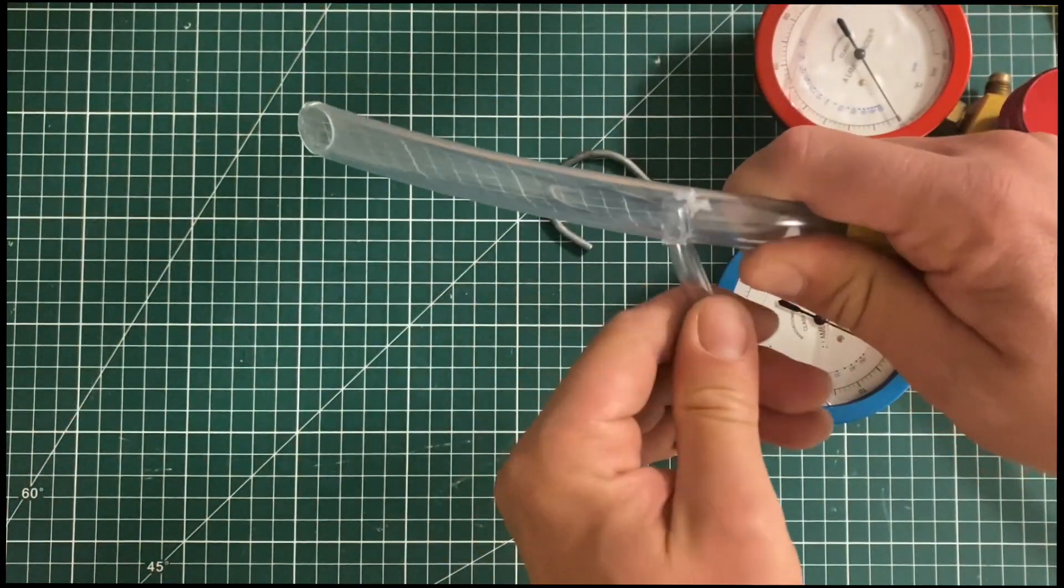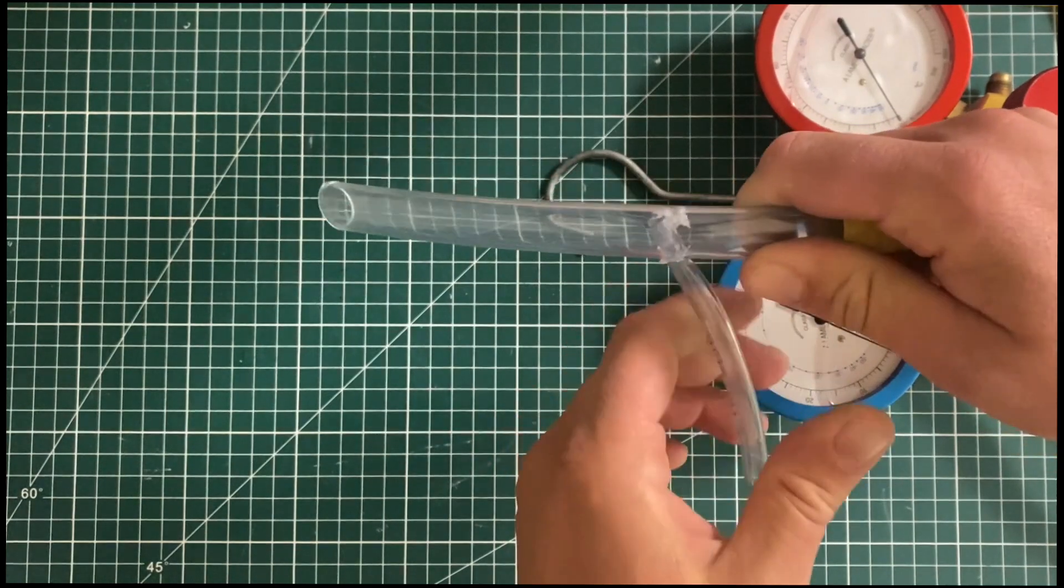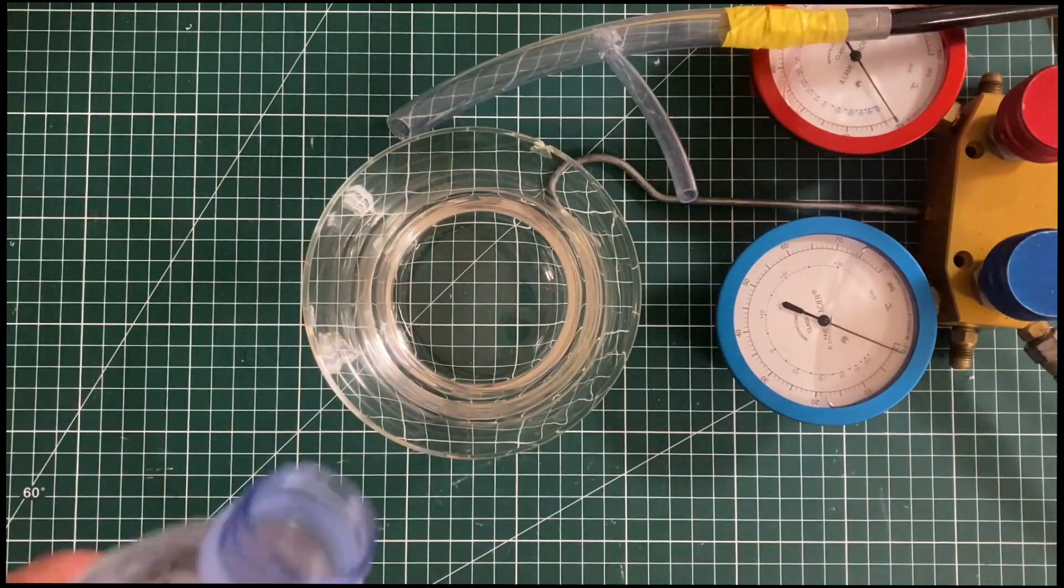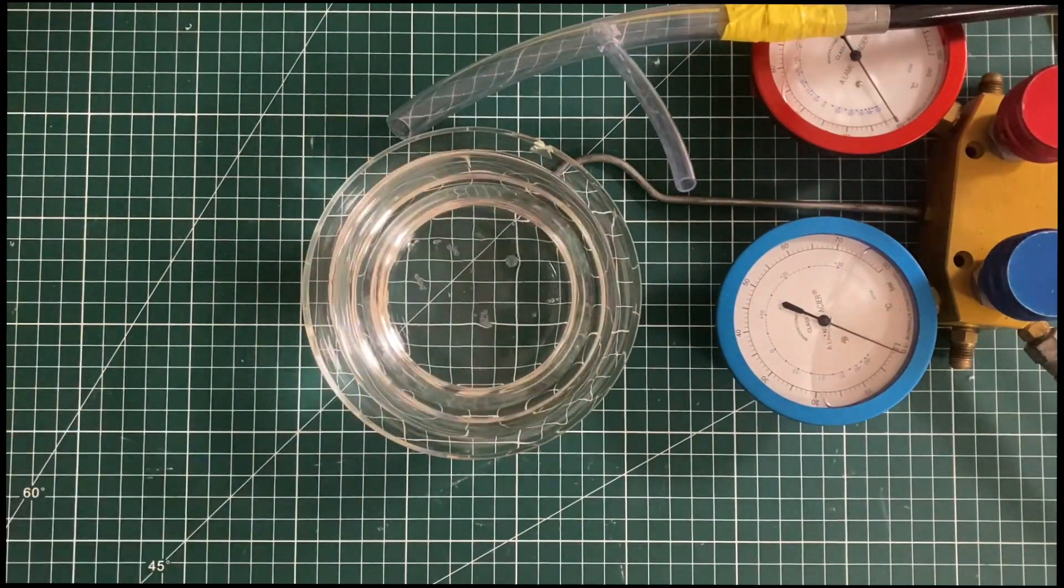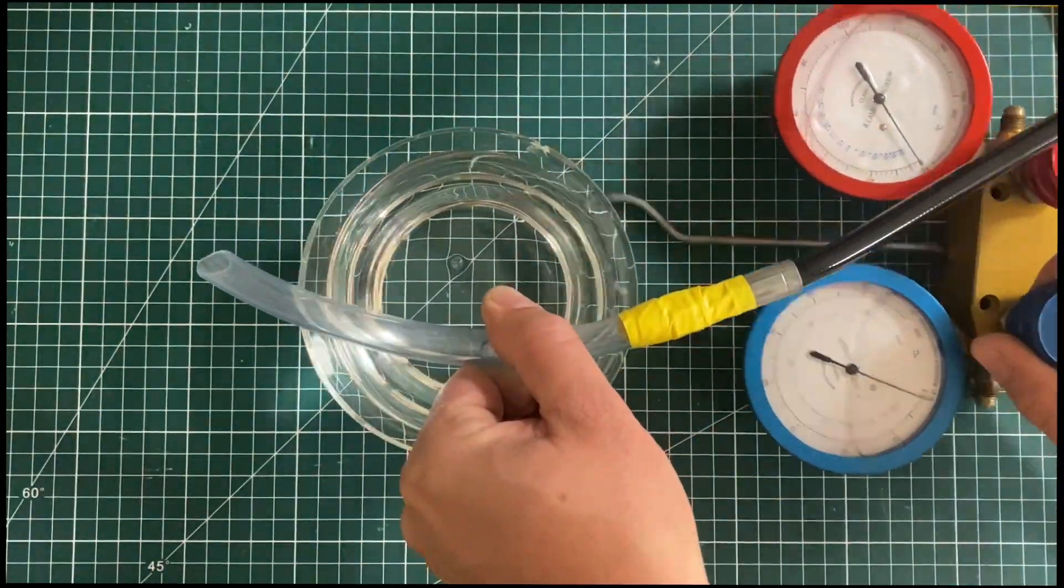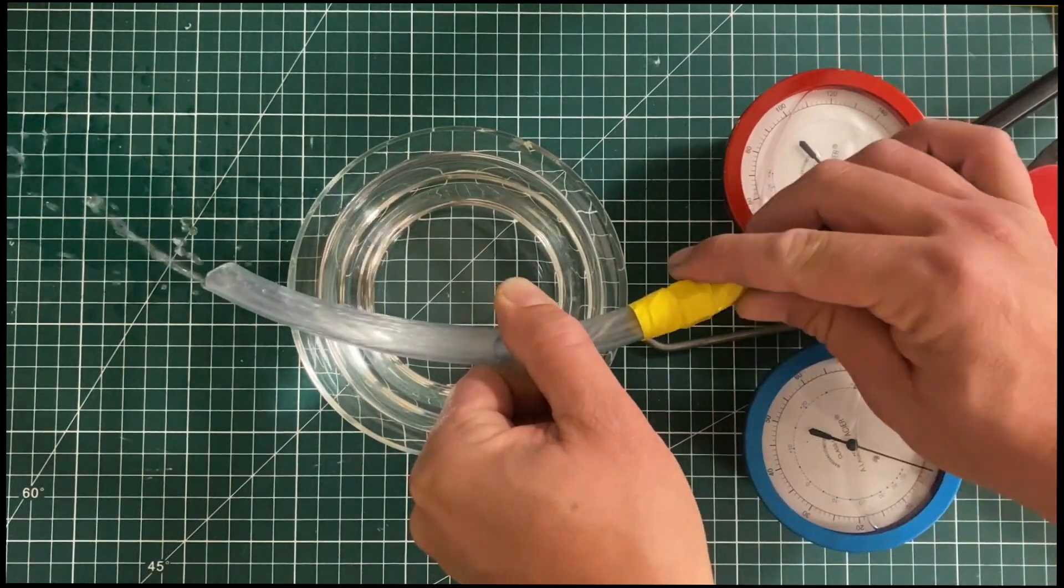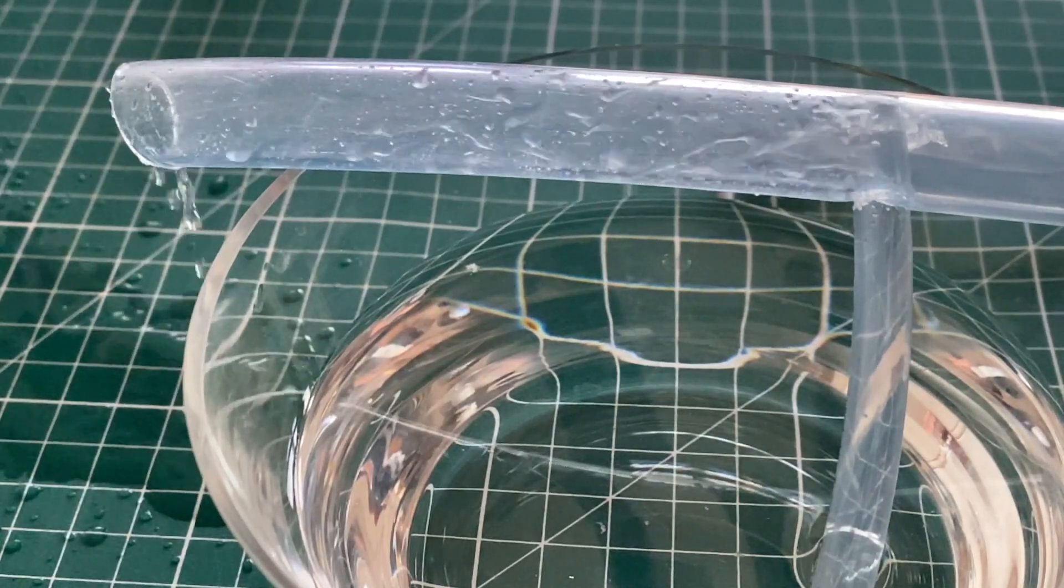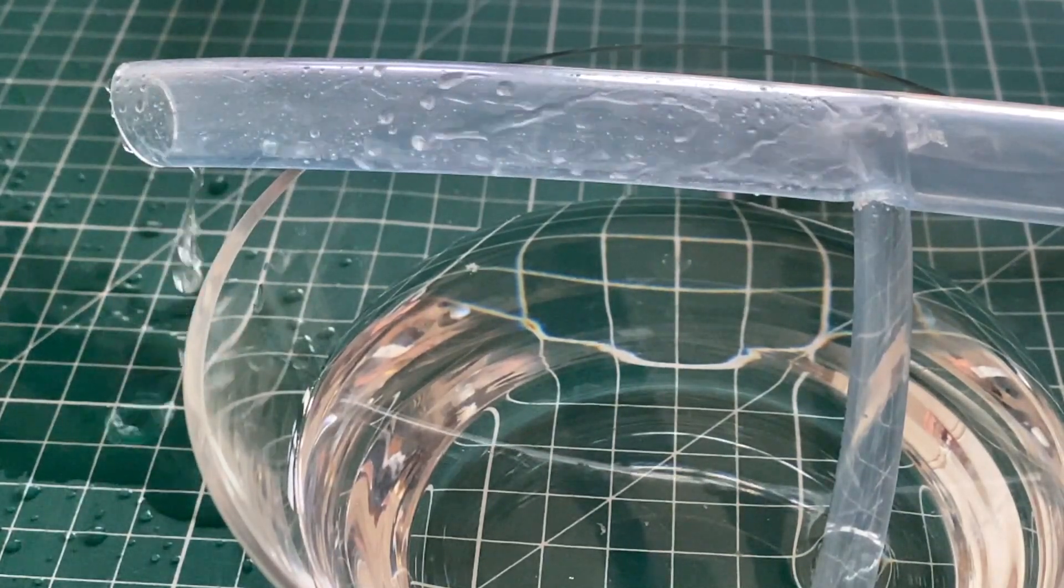We're going to use CO2 gas for the primary mass flow of our ejector. Water is used as secondary mass flow. When CO2 comes inside the ejector, an expansion occurs that allows the lift of secondary mass flow before being mixed to the CO2 in the diffuser.